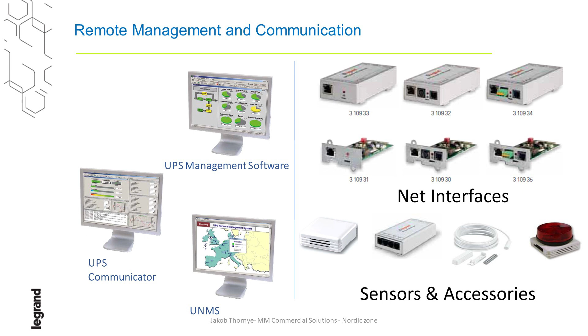But in many cases, we actually see that people want the UPS and the bypass switches in one room, and then have a separate room for the batteries behind. It can even be on a different floor level. Normally we do not recommend more than 70 meters between them, which is still quite far, simply due to the loads on the DC. The DC cabling between this can have some impact on the rest of the installation, so we have to be a bit careful with external battery banks.